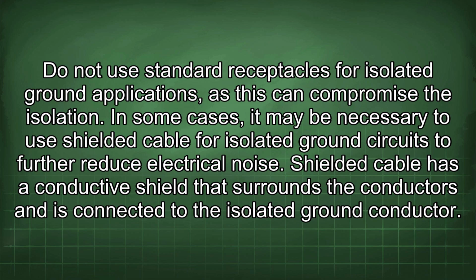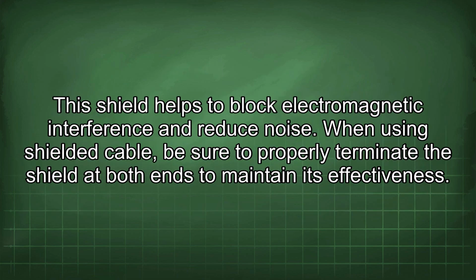In some cases, it may be necessary to use shielded cable for isolated ground circuits to further reduce electrical noise. Shielded cable has a conductive shield that surrounds the conductors and is connected to the isolated ground conductor. This shield helps to block electromagnetic interference and reduce noise. When using shielded cable, be sure to properly terminate the shield at both ends to maintain its effectiveness.